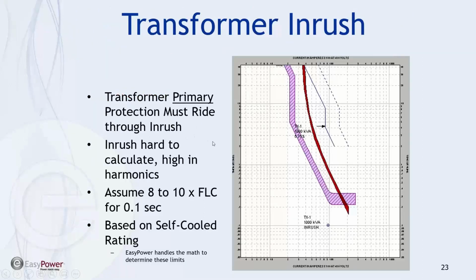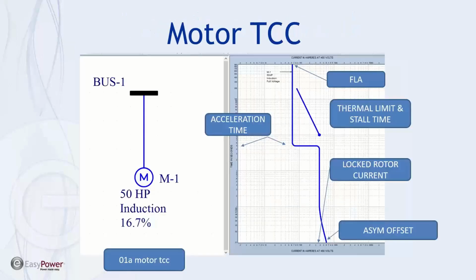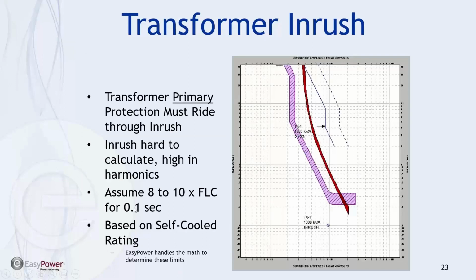I referred to the Inrush plot earlier, but what it amounts to is that during initial energization, there's a potential for current and a host of different harmonics to be launched at the time the transformer is powered up. And that's, as we saw in the data block for the curve, represented based upon some multiple of full load current and some delay time. In this case, I think it was 0.1 seconds. And we want to make sure our protective devices will not be sensitive to that particular current and time element. So for primary protection, we must have the protective devices up and to the right of the Inrush plot.